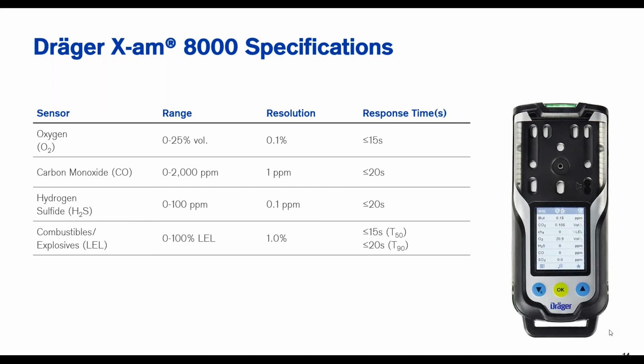But they had a single gas ammonia sensor, and the T90 response time for that was 300 seconds, 5 minutes. I can almost guarantee you there was a lot of pencil whipping going on at that point, because that would mean if I'm going into a vertical space, I'm waiting 5 minutes, getting my reading, dropping it down four more feet, waiting 5 minutes. Let's just be honest, it's a long time. So we've come a long way. I mean, 5 minutes to less than or equal to 15 seconds, less than or equal to 20 seconds. That just means that's the max.